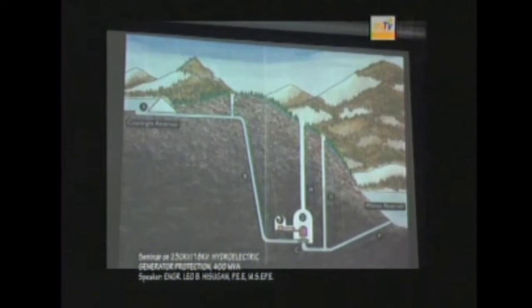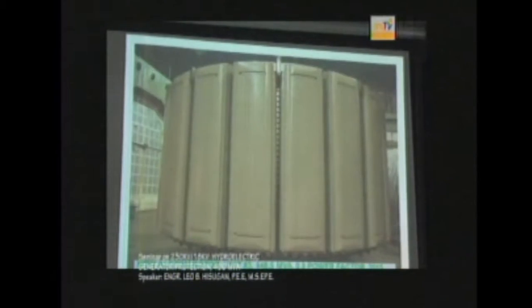So the cable here, the 230 cable from the transformer goes up to the switchyard here. This is the 230 kV switchyard, and this is like 1,500 feet. Okay, so that cable, 1,500 feet, there's 9 of them, and it's costing us $1 million US to buy this all the way from Oslo, Norway. One of the very tricky design of the switchyard on the top of the mountain is that the snow goes high.